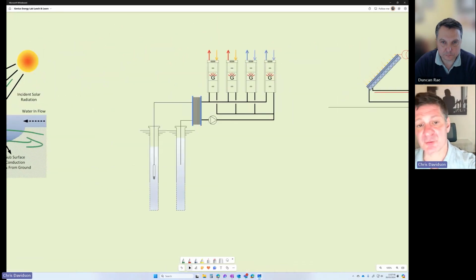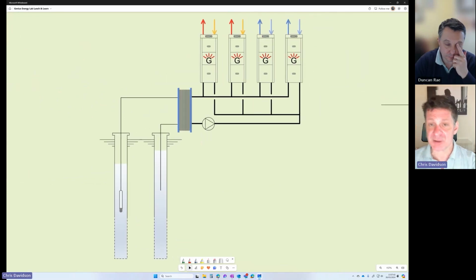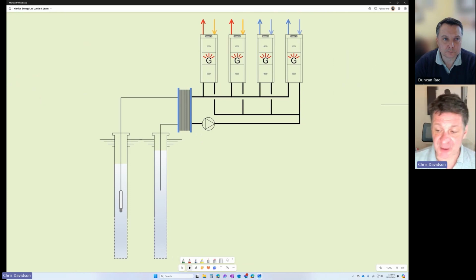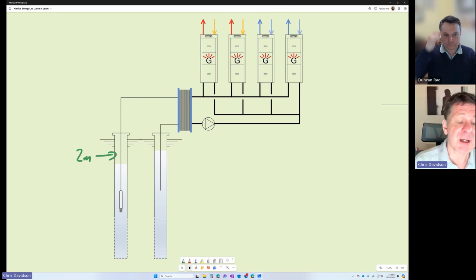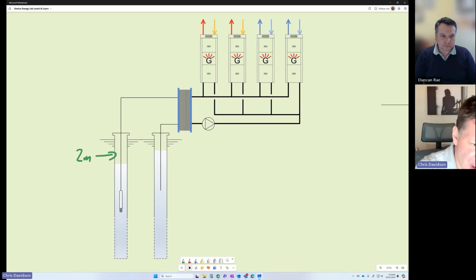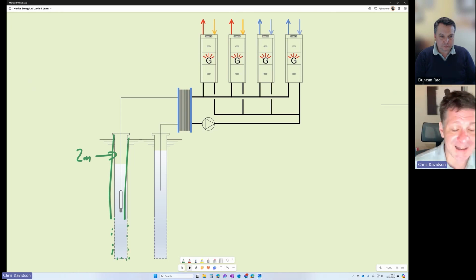There is an alternative to closed loop, which is open loop. Now, I've drawn it here using water wells. So we're taking water from the ground, we're running it through some heat exchangers, and we're putting it back into the ground again. These boreholes for water wells are much, much bigger in construction than the closed loop alternative. They could be up to a couple of meters in diameter, more commonly 600 mil, but up to a couple of meters. They can be typically 100 to 150 meters deep, and they've got some serious construction in them. So they could be lined in steel, stainless steel. They could have some filtration and packing involved in them. They've also got pumps down there to take the water up through the heat exchangers and back into the ground.